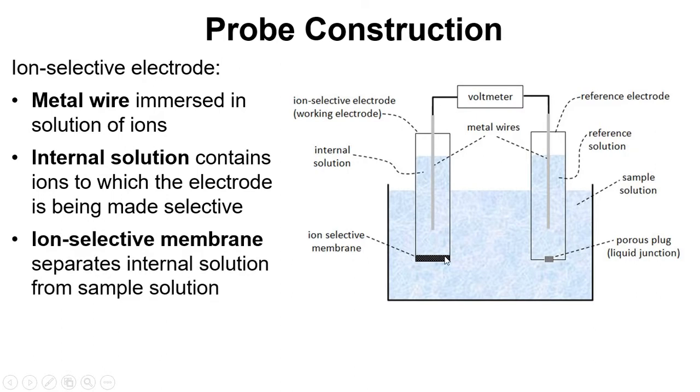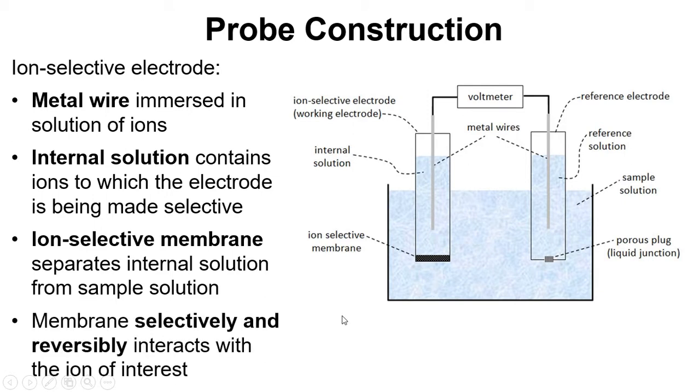The membrane here separates the internal solution from the sample solution. And it exhibits a selective and reversible interaction with the analyte ion, the ion that we're interested in measuring.